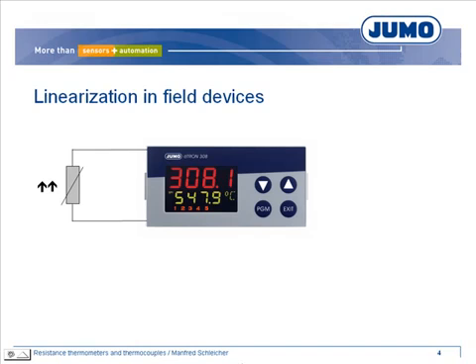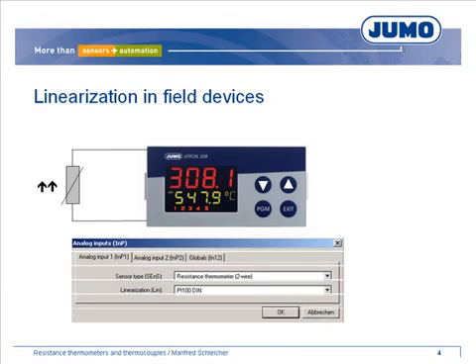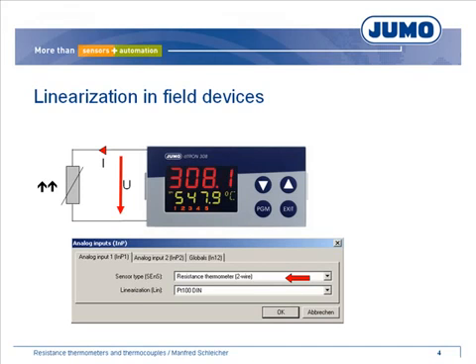After the connection of a PT100 to a field device as an example, we select resistance thermometer as sensor type for the corresponding input. The field device uses a defined direct current. On the basis of the dropping voltage and Ohm's law, the resistance is calculated. Different linearization possibilities are stored in the field device. When the linearization is set to PT100, the device calculates the temperature based on the resistance value.